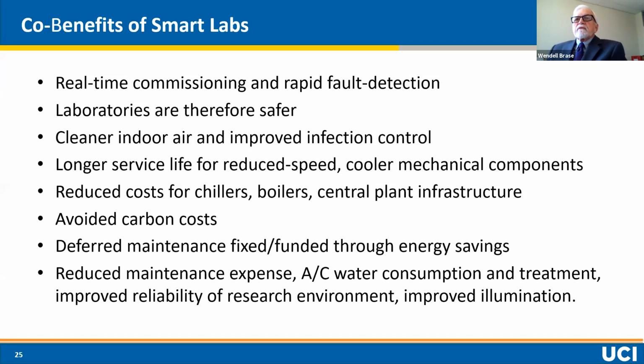The next benefit is longer life from reduced speed. Everything that's turning, heating, or cooling is basically running at half speed. Some of those devices follow the square rule, meaning they'll last not twice as long at half speed, but four times as long. Some actually follow the cube rule, like exhaust fans on lab buildings - they'll last eight times as long.